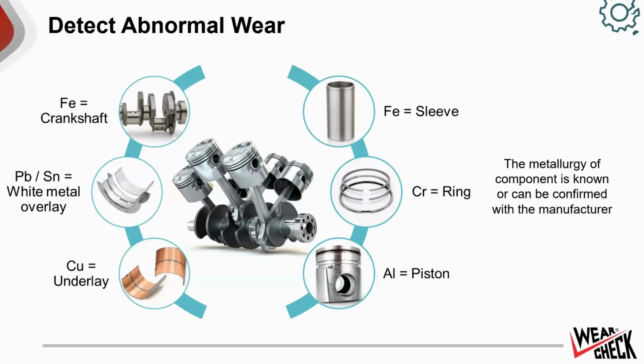So how do we do that? Well, the metallurgy of particular components is known, or we can find it out by engaging with the manufacturer. So, for example, we know that pistons are made of aluminium alloys, plain bearings contain lead, thrust washers and bushes usually contain things like copper, and shafts, gears and roller bearings usually consist of different alloys that contain iron. So we're looking at steels.